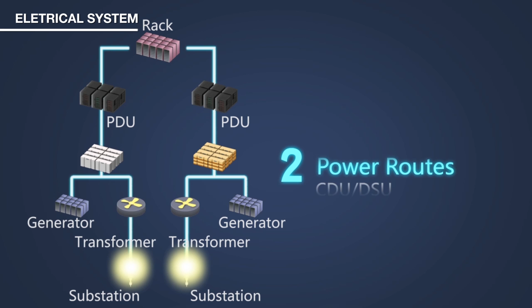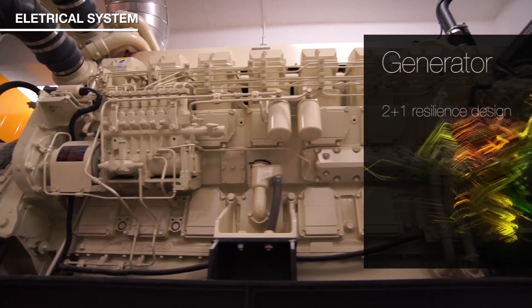Our 2N configured power supply meets Tier 3+ carrier class data center standards, such that all supply components including transformers, generators and UPS are 100% redundant, and all connections have dual paths. The power supply is supported by reliable and resilient UPS systems, backed up by generators equipped with high-volume fuel tanks continuously refilled by oil companies. This configuration prevents power outage as a result of any unforeseen occurrence.